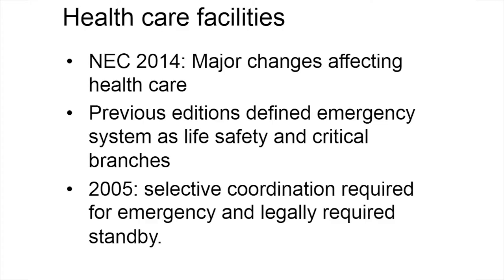Now we'll look briefly at healthcare and some of the things that are different about hospital design versus design of emergency systems in other types of facilities. There were some major changes in the 2014 code. Prior to 2014, the life safety and critical branches of hospital systems were the emergency system, and as such, they fell under Article 700.